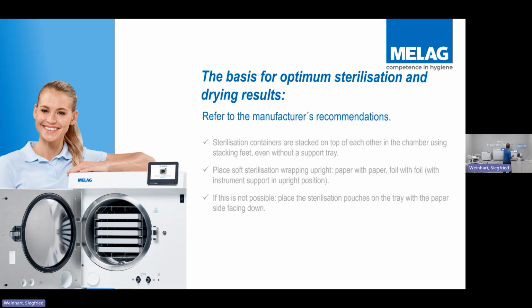Sterilizing containers. Okay, your practice may well be looking at things like these, which are containers. Now, what these do, in essence, is negate the need for any pouches. So the idea is you would either use a cassette, a clip tray, or something like that within the actual box, or you'd place loose instruments in the box. Ideally, you want to be looking at instruments that you're not going to use all the time. Now, the idea with these is once the instruments are loaded in there, that whole box would go into the autoclave. You'll notice there's no rack in there. I've taken the rack out, so you don't put the rack in.